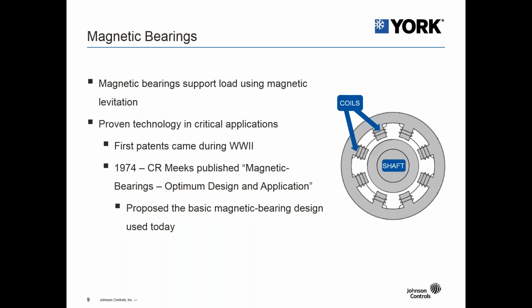So just a quick overview of magnetic bearings. The magnetic bearings support the load using magnetic levitation, so there's no contact with the shaft. And this is a proven technology that's been used in critical applications, like I've mentioned earlier, on the Navy systems. And it's not a very new technology. We first saw patents coming out around World War II, and then in 1974, the publication Magnetic Bearings: Optimum Design and Application is pretty much the basics and the basis of what's used today in magnetic bearing technology. So there hasn't been a big shift in the technology since the 70s.